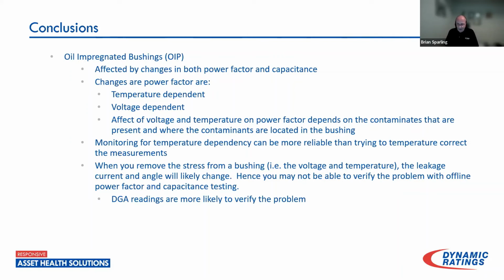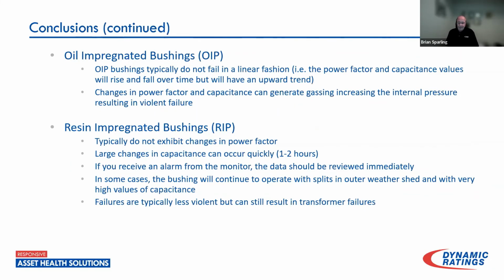Hence, you may not be able to verify the problem with offline testing, power factor and capacitance testing. That has happened in the past. One of the tests of last resort, as I call it, for understanding the condition of the bushing is to do a DGA test on the oil of the bushing. That, in my experience, has seen some real eyebrow-raising values of combustible gases in what were questionable bushings. And I'm talking about tens of thousands of parts per million of hydrogen in the oil of bushings, which were just waiting to explode. But again, DGA is the test of last resort when all else has you scratching your head.